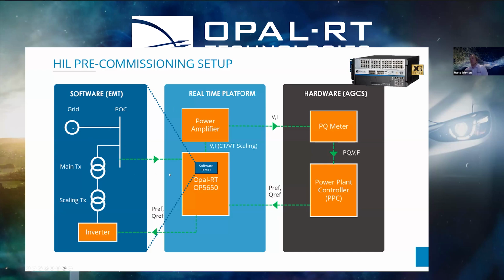And then from there, we use a power amplifier which basically emulates what would be CTs and VTs at the point of connection, scaling down the voltage and current to something applicable to the power quality meter. Typically this would be around 110 volts and 1 amp. Those signals coming out, and you'll see our setup a little bit later, are the actual voltage and current signals that a power quality meter would see.